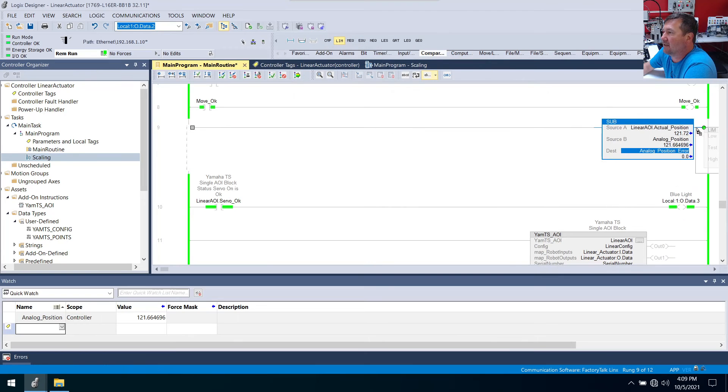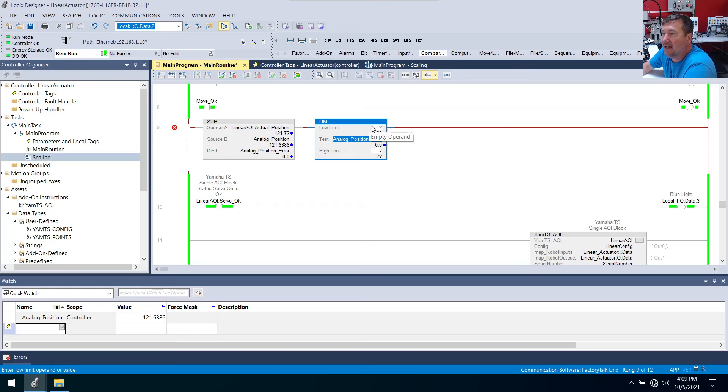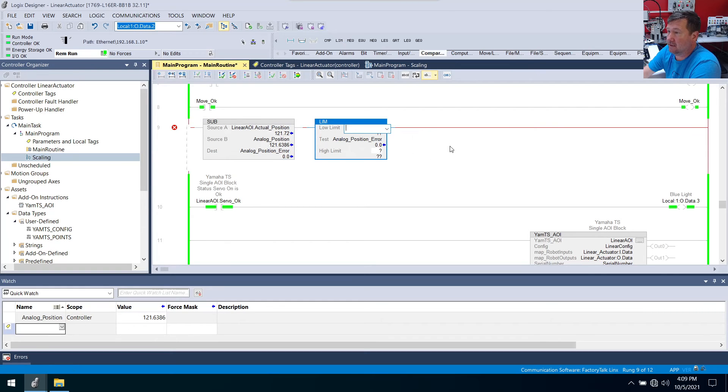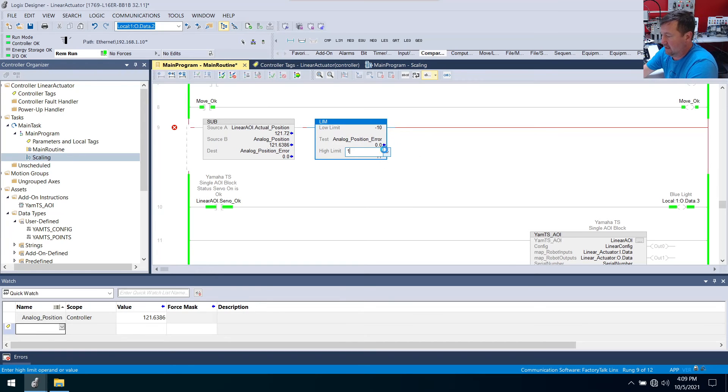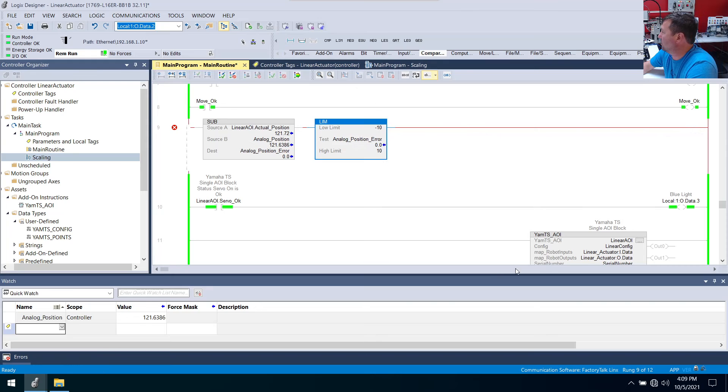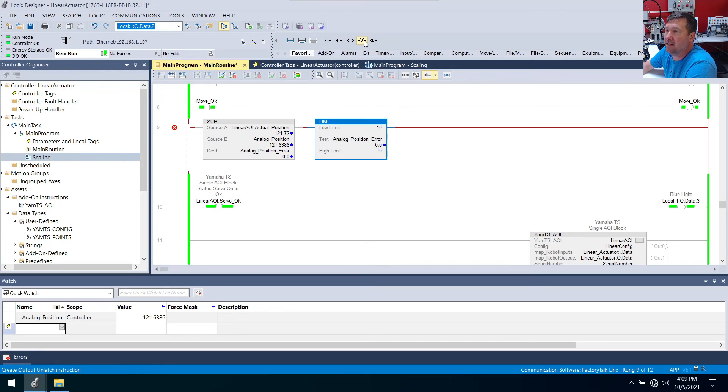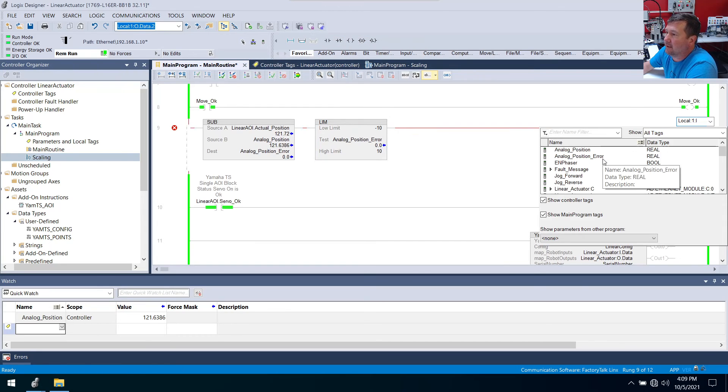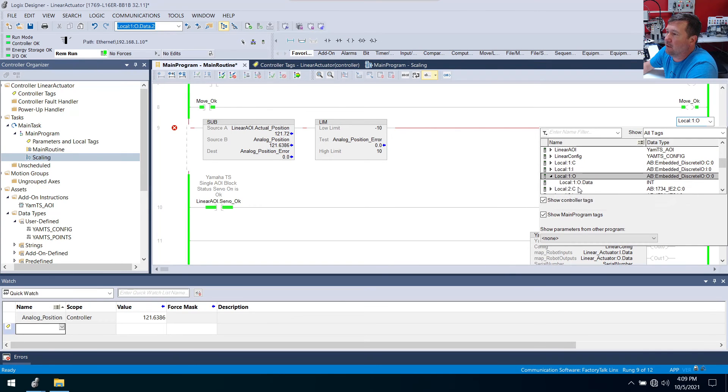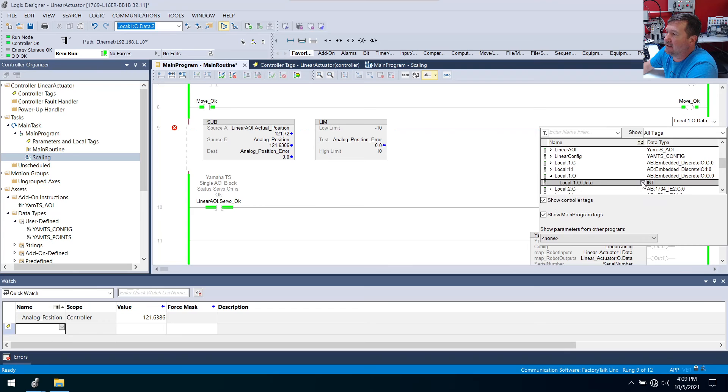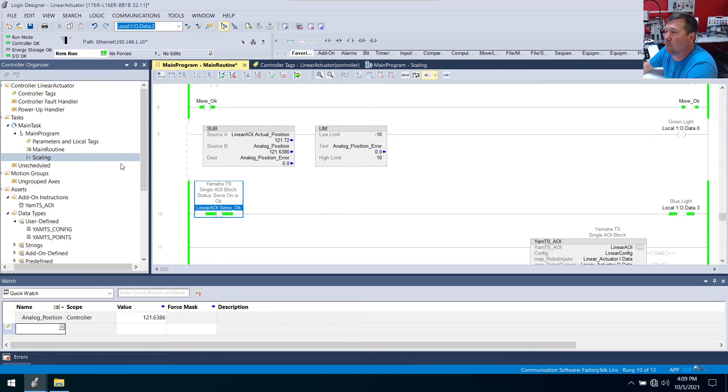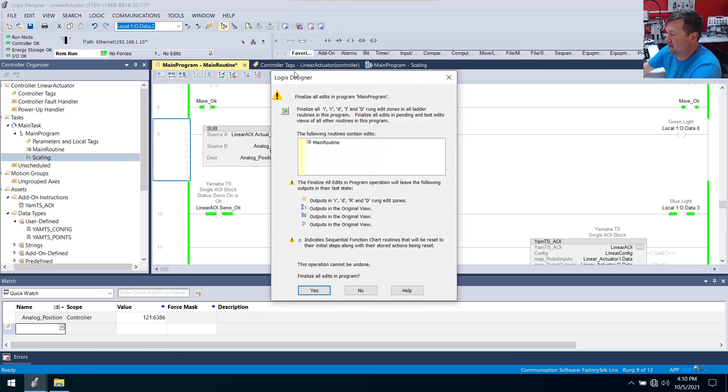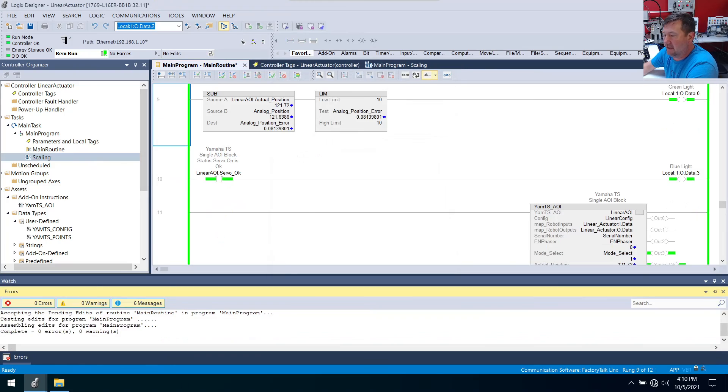And we are going to subtract this AOI, which is linear AOI. We're going to subtract the actual position. Source A will be linear AOI dot actual position. And then source B is going to be that analog position. And then our destination is going to be our analog position error. And then we're going to add a limit instruction. So we're going to go to our compare tab and bring down a limit. And our test is going to be this error that we have. And just so we have something, we're going to make our low test minus 10 and our high test 10.